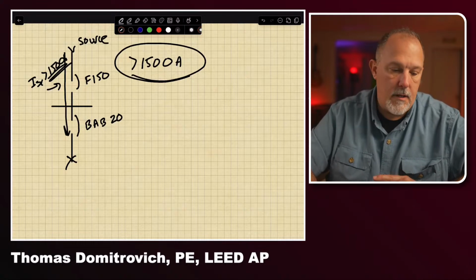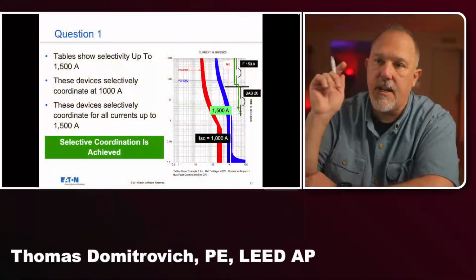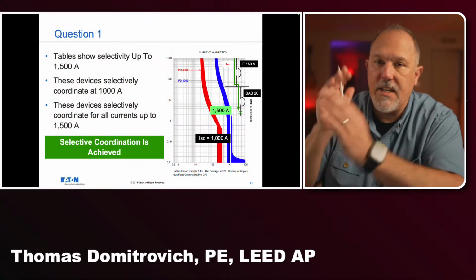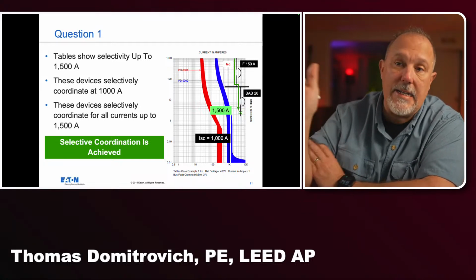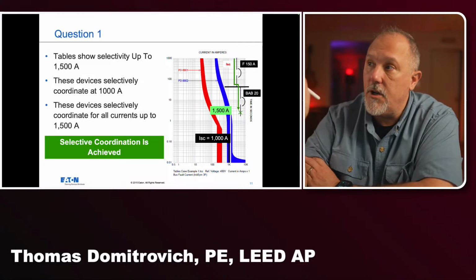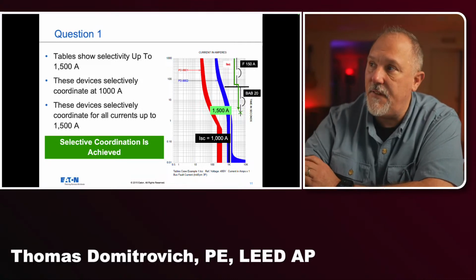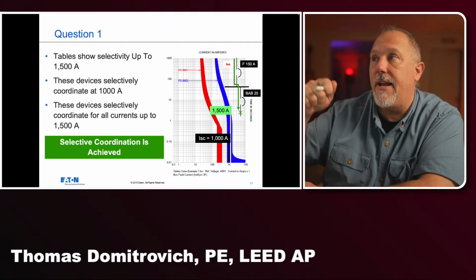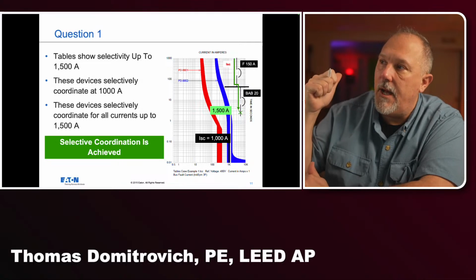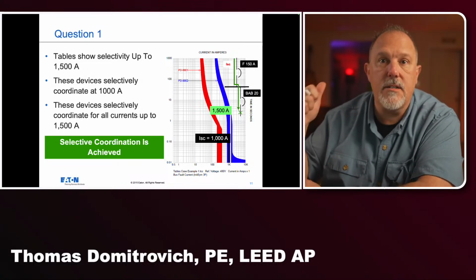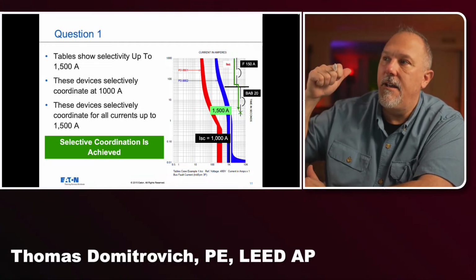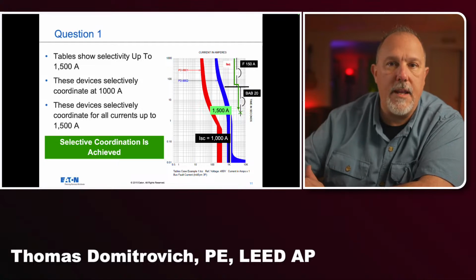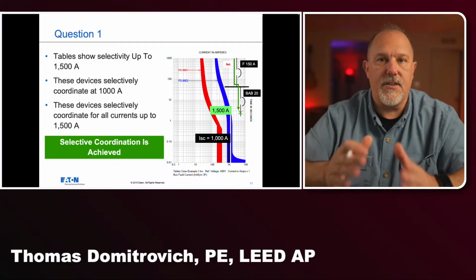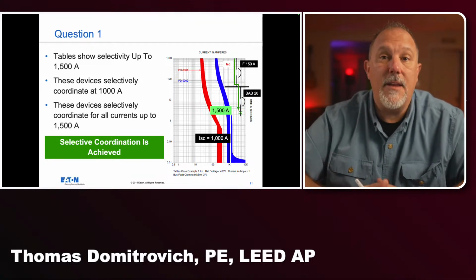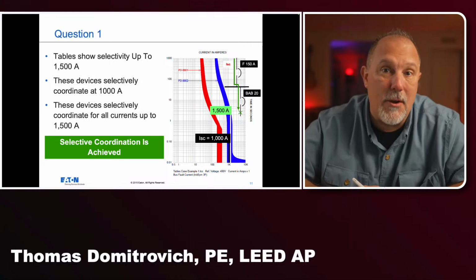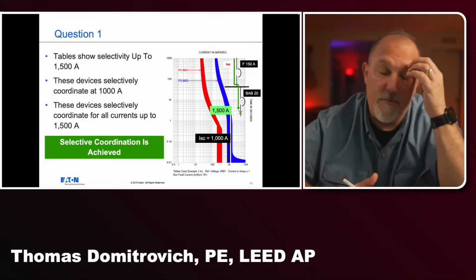Now, if I think about that with regard to the time current characteristic curve, then based upon the tables, I could plot that 1500 amps and say, look, I selectively coordinate for fault current of 1,000 amps because it's less than the 1500 amps. It is into the instantaneous region of that upstream F150, but I know because of the selective coordination tables, which are based upon the testing, that the downstream breaker is going to open and the upstream breaker will stay closed. And hence I have selective coordination for that three-phase bolted fault current value. Now, 1,000 amps of three-phase bolted fault is pretty daggone low. And it's probably very rare.